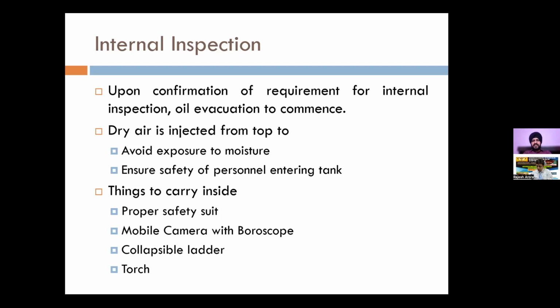Because there have been some incidents where a person has gone in for internal inspection, and due to less oxygen content inside the tank, and moreover, if there is any fault which has happened inside, even after you evacuate all the oil, some of these fault gases may remain inside the tank, which can cause suffocation of the person who is entering. So earlier we used to mostly use dry N2, but now we have shifted to dry air to ensure that our personnel are safe when they enter the tank.